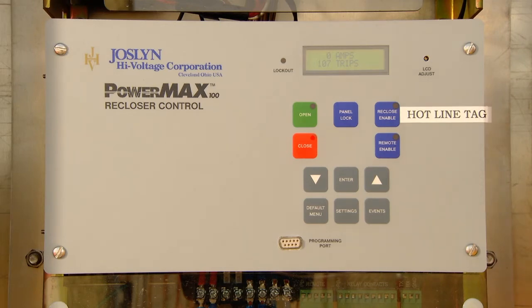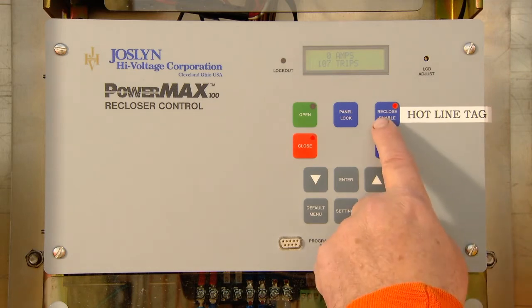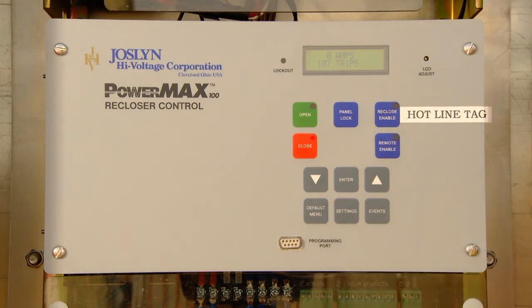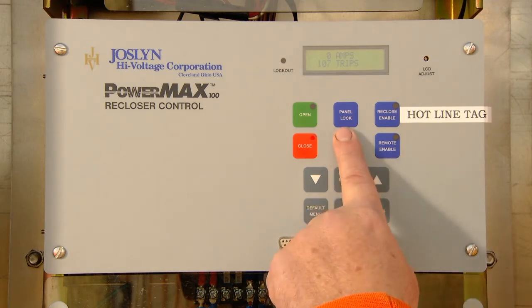Under normal conditions, the Reclose Enable LED would be on. This will allow it to go through its normal operations for whatever it is programmed for to reach lockout. If you wanted a hotline tag or hold off to allow this to go only one shot to lockout, on the older panels, you would turn off the Reclose Enable. More recent panels feature a pre-programmed button marked Hotline Tag, located roughly here on the newer panels.